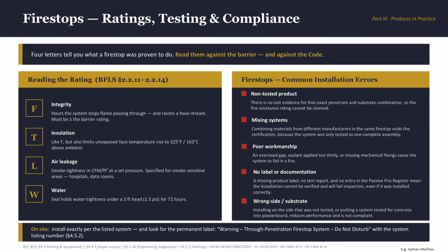As basic as that. Second is mixing systems. Remember we said fire stop should be tested as one unit? This is why. If you take materials from different manufacturers and combine them together in the same fire stop, you void the whole idea of certification, because that combination was never tested together. Each piece may have its own certification, but they were never tested together as the whole assembly.